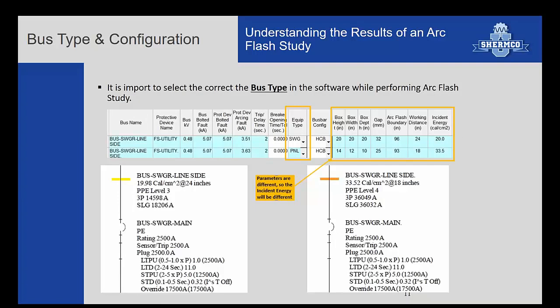So we did a little example to show the difference. Here we put a panel board and a switchgear on the same bus, and you'll notice that the switchgear had 3,510 amps of arcing current, where the panel, which had smaller dimensions, had more arcing current, less gap. And if you notice, it made the results significantly different.